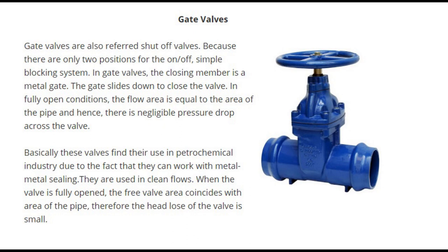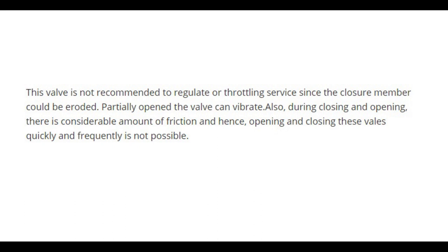Gate valves are used in petrochemical industries because they can work with metal-to-metal sealing. They are used in clean flows; when fully opened, the free valve area coincides with the area of the pipe, so head loss is small. However, they are not recommended for regulating or throttling service since the closure member could erode. A partially open valve can vibrate, and opening or closing these valves quickly and frequently is not possible due to considerable friction.